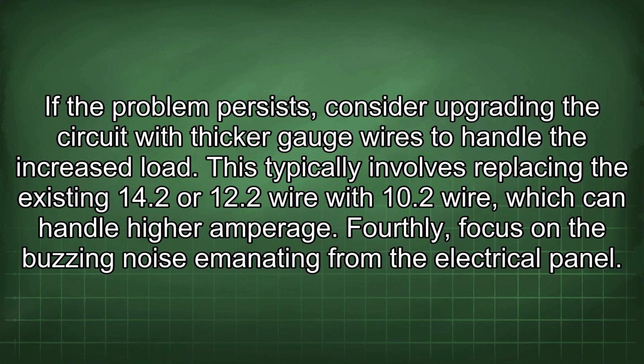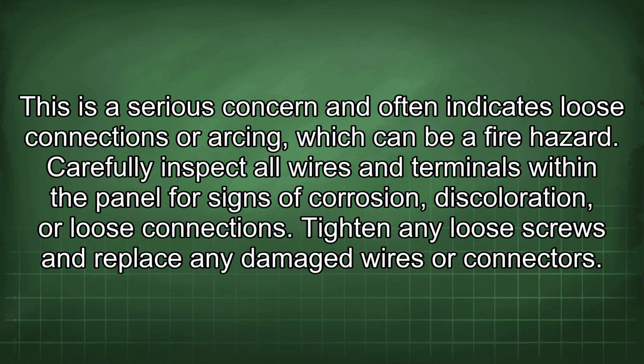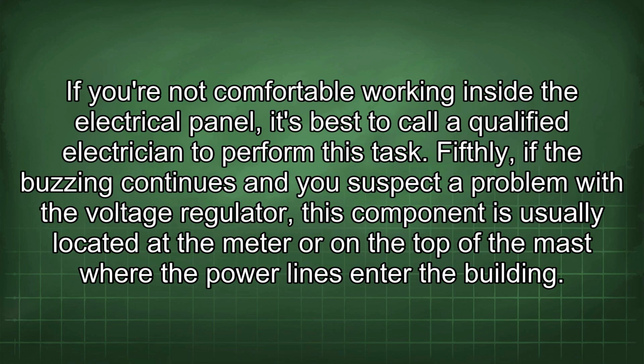Fourthly, focus on the buzzing noise emanating from the electrical panel. This is a serious concern and often indicates loose connections or arcing, which can be a fire hazard. Carefully inspect all wires and terminals within the panel for signs of corrosion, discoloration, or loose connections. Tighten any loose screws and replace any damaged wires or connectors. If you're not comfortable working inside the electrical panel, it's best to call a qualified electrician to perform this task.